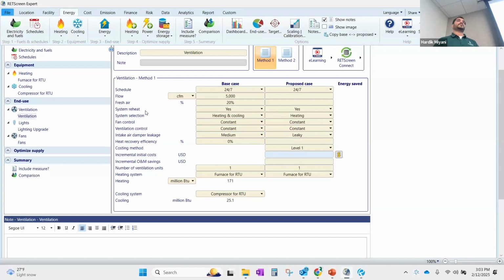System reheat is, suppose you have a rooftop unit and before it enters a space, there is a small terminal unit like variable air volume, fan powered boxes with reheat. So those are the different types of terminal units that adjust the amount of airflow and the heating cooling supply air depending upon the thermostat set points, right? Suppose you have a rooftop unit that is serving two spaces, this one and the other one. This is calling for cooling, the other one is calling for heating, right? What will the rooftop unit do in that case?